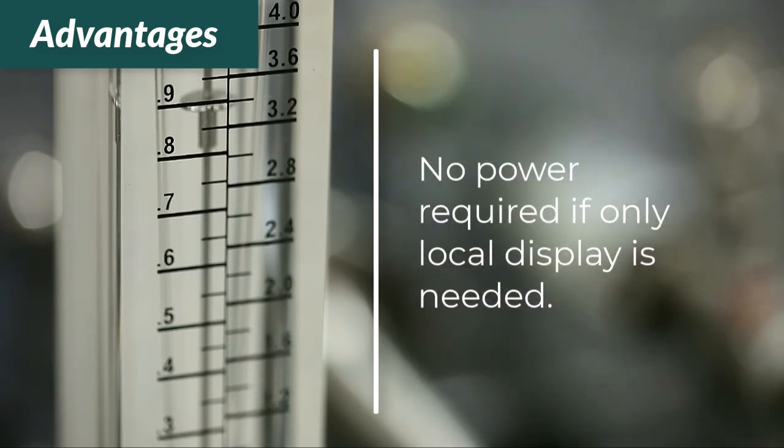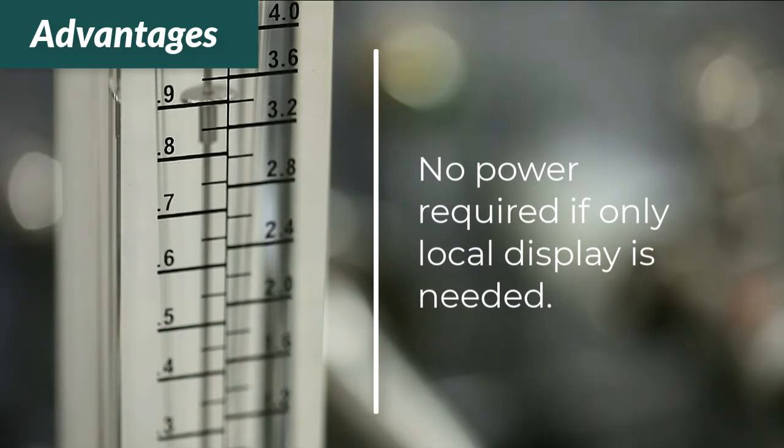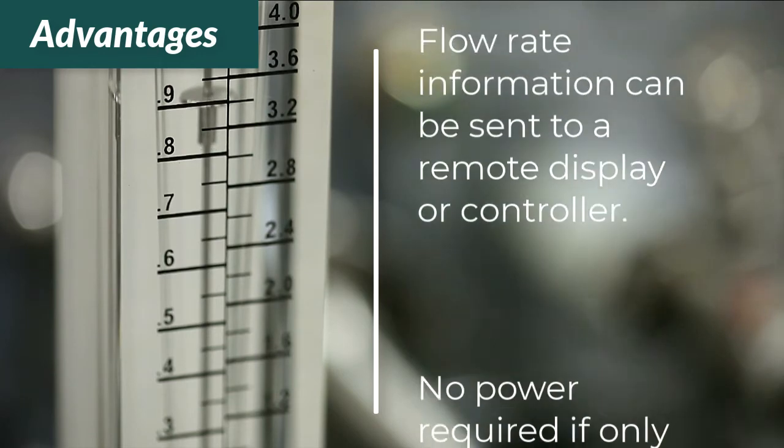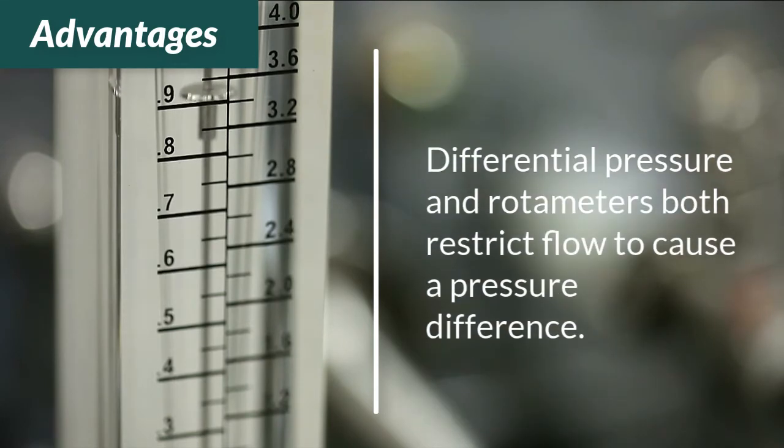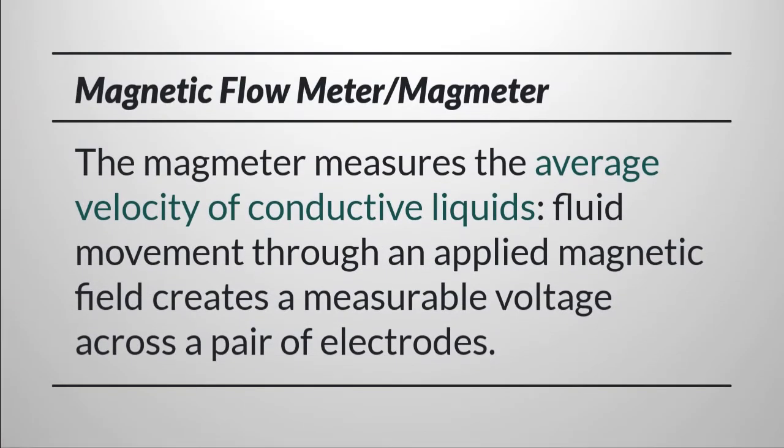If only local display is needed, no power is required as the float position can be seen through a transparent tube. The float can be magnetically coupled to a dial indicator or an electronic transmitter can be used to send flow rate information to the remote display or controller. Differential pressure and rotameters both restrict flow to cause a pressure difference. One advantage of magnetic meters and ultrasonic meters is that they don't restrict flow.